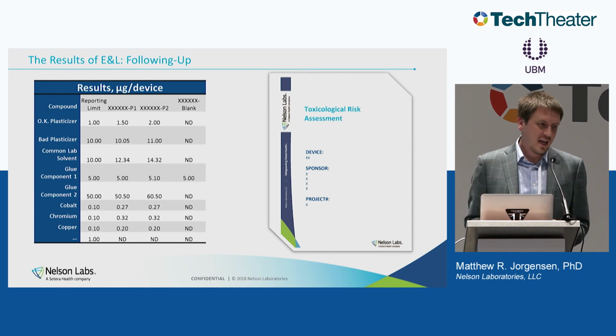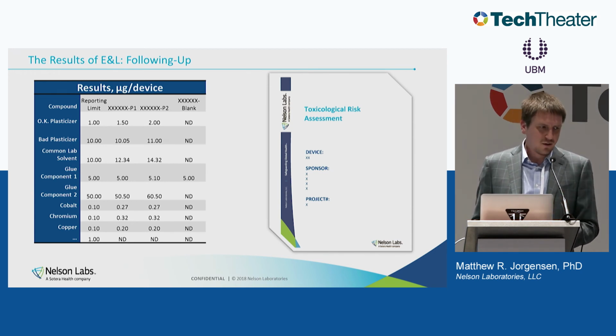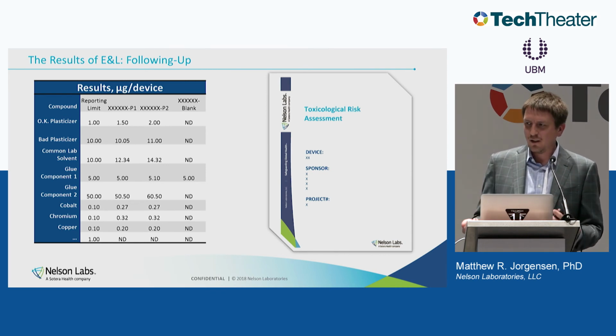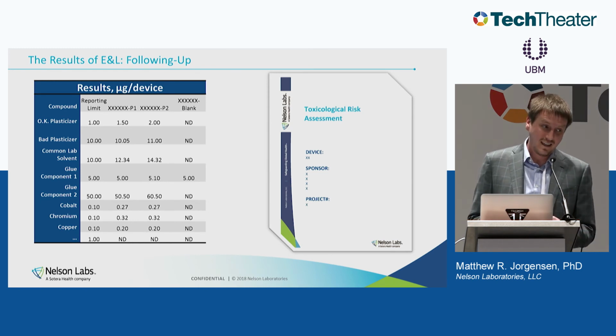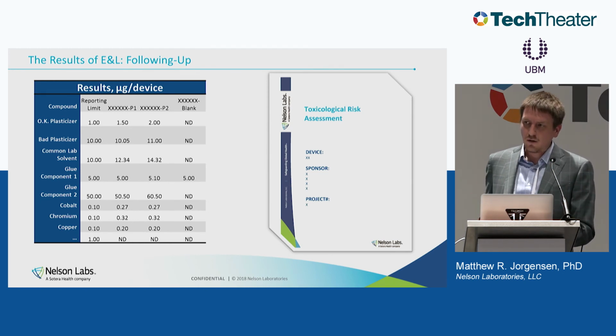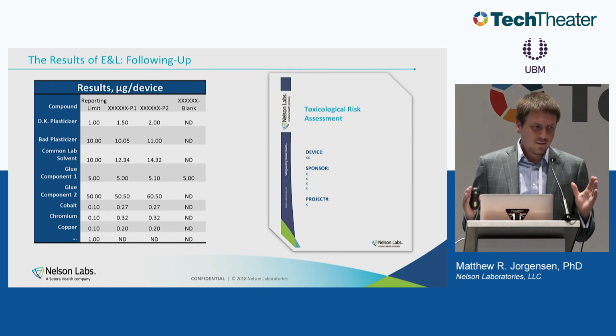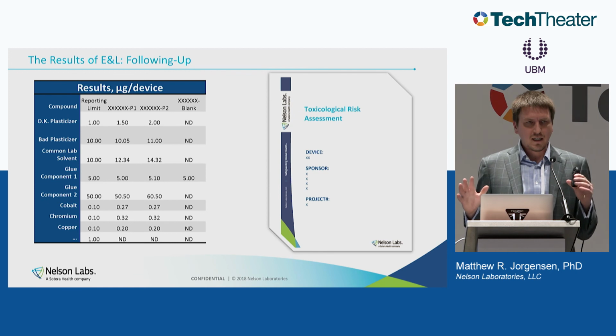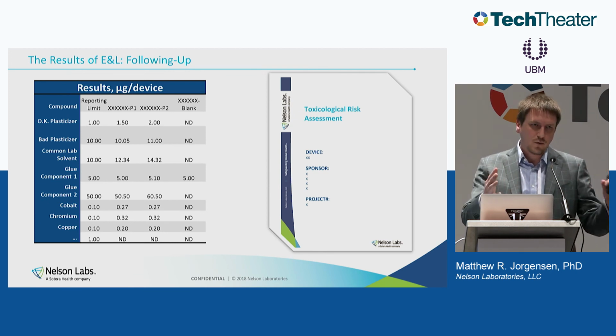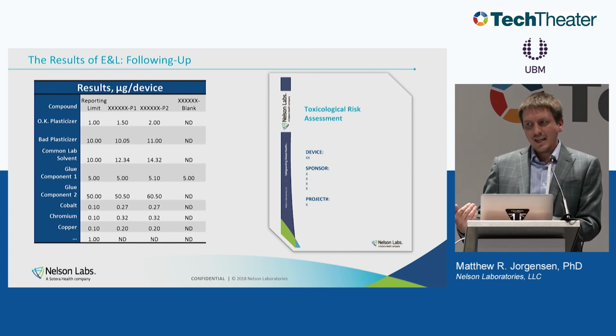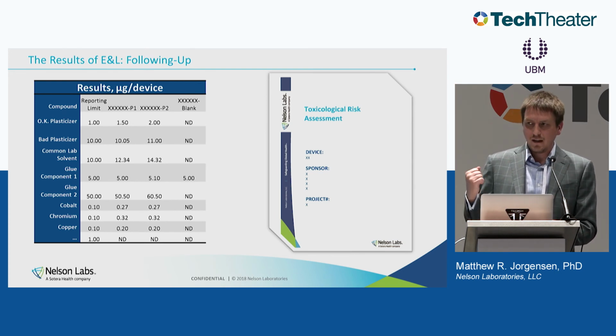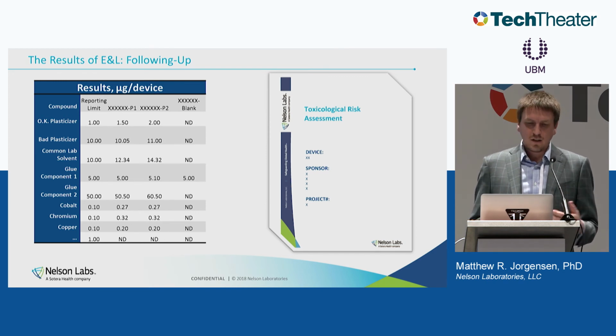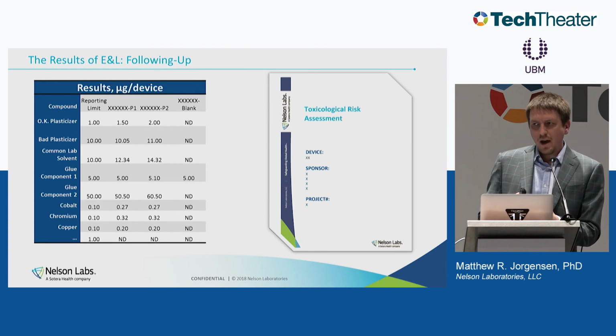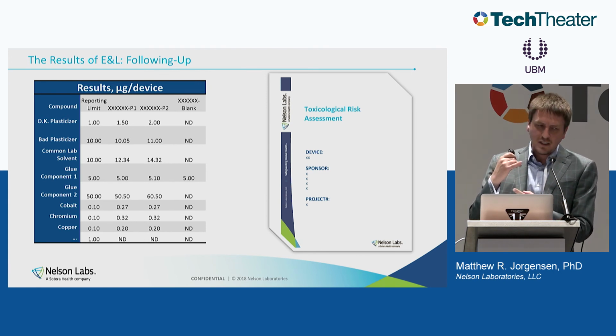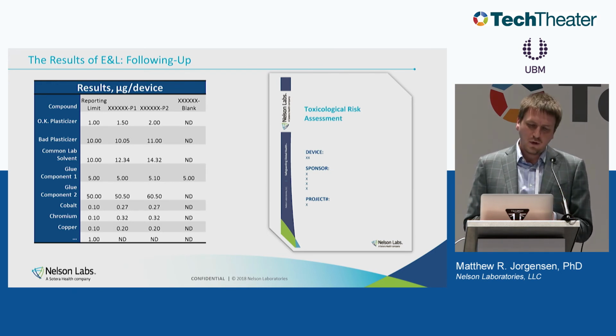If you just give the FDA or TÜV or DEKRA these chemistry results, they'll just laugh at you and throw it back. They say, okay, well, you have to tell us what this means, right? Somebody that's qualified needs to tell us what this means. And that's where a toxicological risk assessment comes in. So if you're using chemistry to address biocompatibility, you have to remember it's a two-phase process. One is the art and beautiful science of chemistry, and after that somebody qualified needs to interpret the results and make a claim about safety. So the toxicologist will say, we've reviewed all of these compounds, and based off of my expertise, the risk of chronic toxicity, subacute toxicity, and so on is low, and it's actually that part that the FDA really cares about.